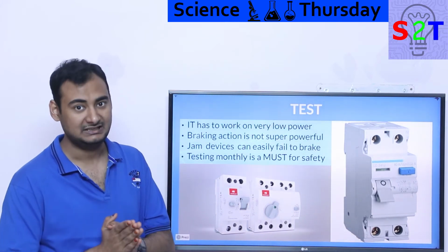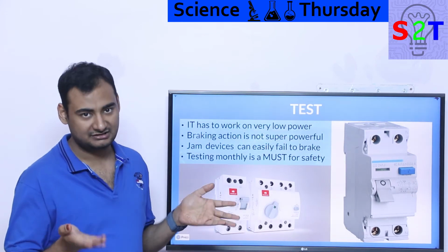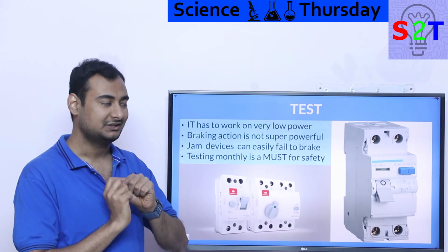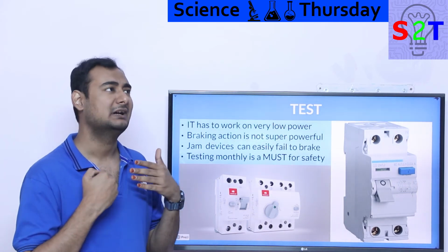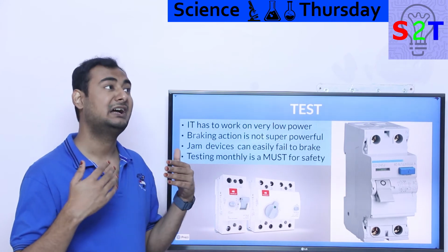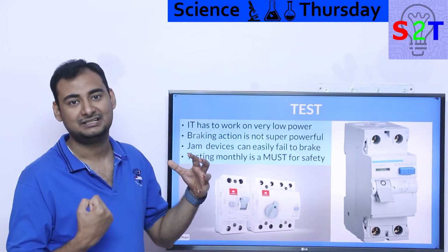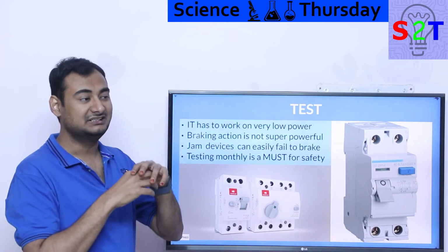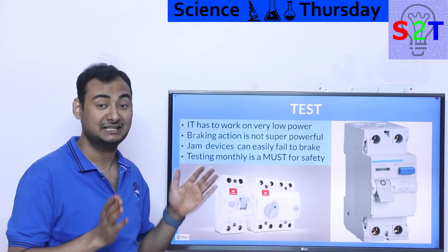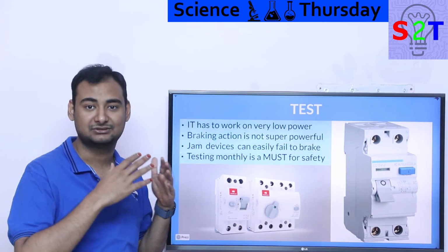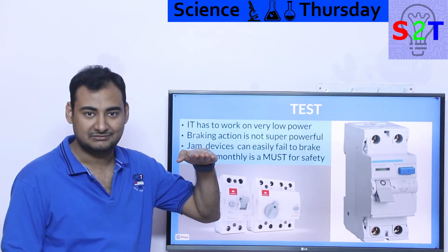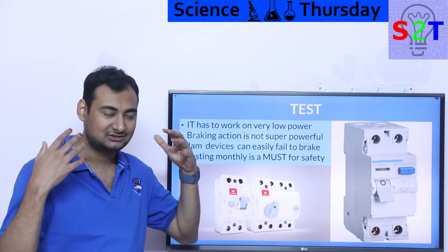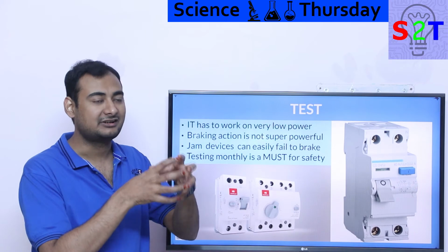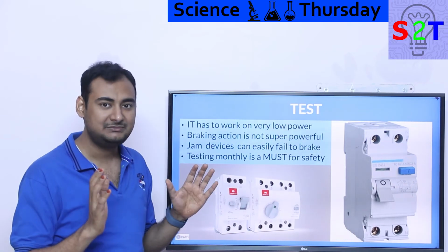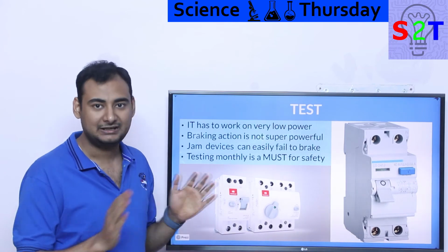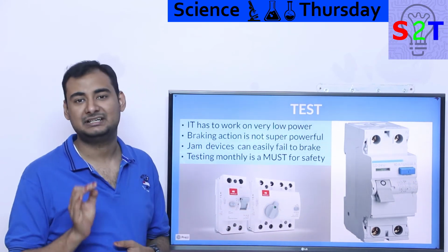Now compare this to the MCB's magnetic coil, which could trigger itself in a short circuit scenario where live and neutral go YOLO with each other. In those sorts of scenarios, the current created could go as high as 50-60 amps to 500 and 600 amps, and that is so much energy that even a basic coil will destroy itself, but it will disconnect. So you do not have to worry about it. And then you have a thermal system, which protects you against slow overdraw of current. The metal will bend no matter what you do. Thermal expansion is such a powerful force. It rips apart railway tracks. So you can understand MCBs have more than enough energy, enough oomph, to break. It will disconnect. You rarely will have a scenario where it does not disconnect.